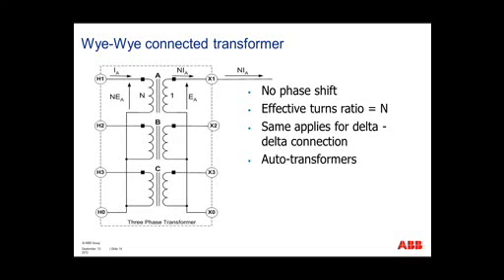So let's look at the connections of a Wye-Wye connected transformer. For a Wye-Wye connected transformer, you'll have the high side, H1, connected to the polarity point of A phase winding of the transformer. H2 will be connected to the B phase polarity point winding of the transformer, and H3, C phase. Your non-polarity points of the windings will be connected to H0, which will be your neutral connection. Similarly, on the low side, X1 will be connected to the polarity point of A phase, X2, polarity point of B phase, and X3, polarity point of C phase.